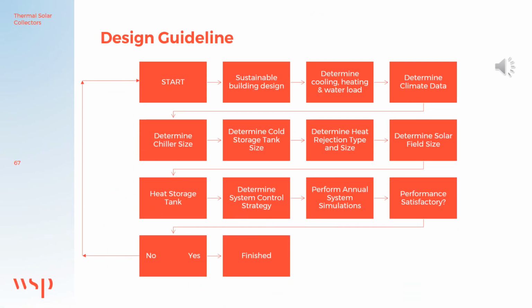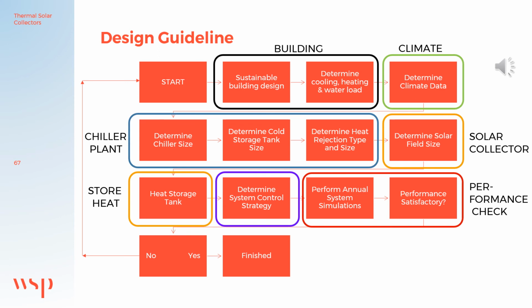When it comes to designing a solar cooling system, there are many different design approaches and methods. This is a condensed overview of a rather complex design process. This manual method can be used as a first design in feasibility studies as well as for a preliminary cost assessment. The methodology starts off with the building itself and a sustainable building design. Once optimized, determine the cooling and heating loads. Then, using the climate data, determine the weather data and radiation parameters. Once that is done, determine the chiller plant size and any chilled or ice water storage. Then calculate the solar heat required and size of the heat storage capacity. Design the plant control system, and lastly perform the annual system simulations, and also determine any backup energy needs and auxiliary power consumption of the solar cooling system.